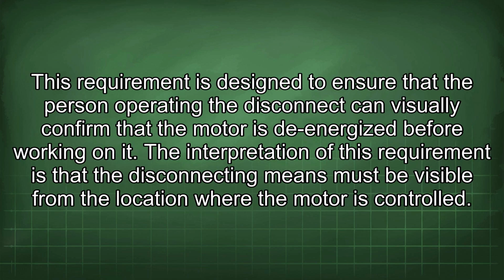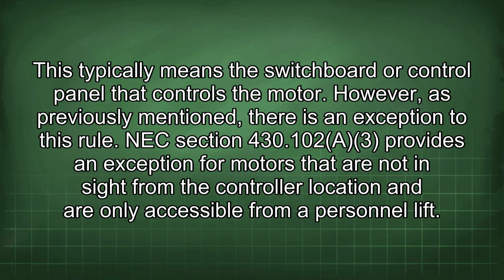This requirement is designed to ensure that the person operating the disconnect can visually confirm that the motor is de-energized before working on it. The interpretation of this requirement is that the disconnecting means must be visible from the location where the motor is controlled. This typically means the switchboard or control panel that controls the motor. However, as previously mentioned, there is an exception to this rule.